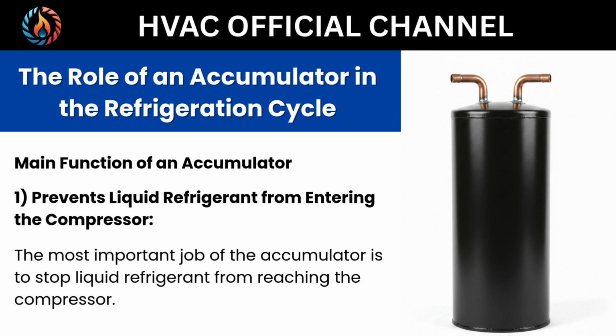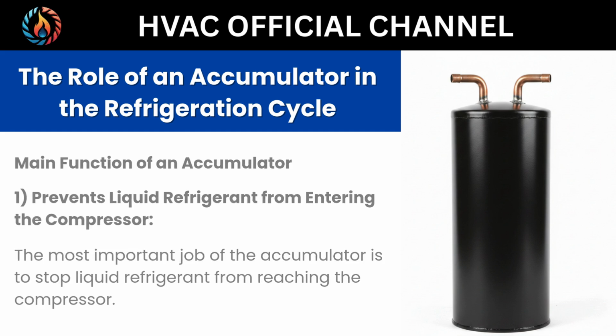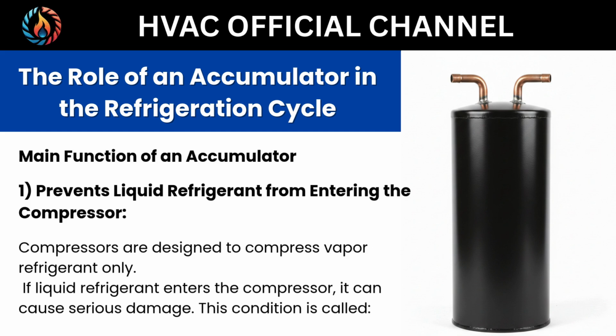Main function of an accumulator: 1. Prevents liquid refrigerant from entering the compressor. The most important job of the accumulator is to stop liquid refrigerant from reaching the compressor. Compressors are designed to compress vapor refrigerant only. If liquid refrigerant enters the compressor, it can cause serious damage.